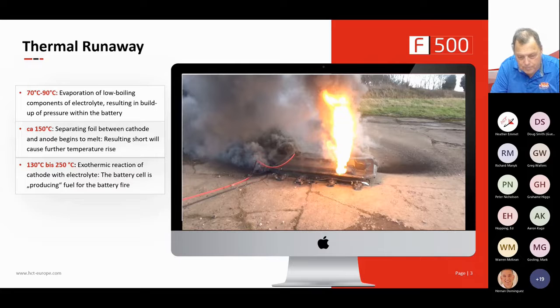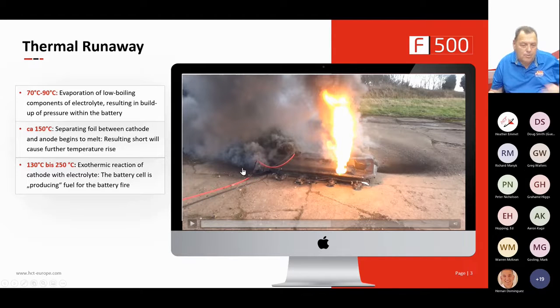Remember, we encapsulate fuel molecules, whether they're in a vapor phase or a liquid phase. So what we have is electrolyte being heated up and going to a vapor phase, and that's what we're seeing being ignited here along with hydrogen. When we hit this, we encapsulate that fuel, cool that area, and take away the flame. Our agent does reduce surface tension and goes into cracks and crevices to extinguish the fire quite quickly.